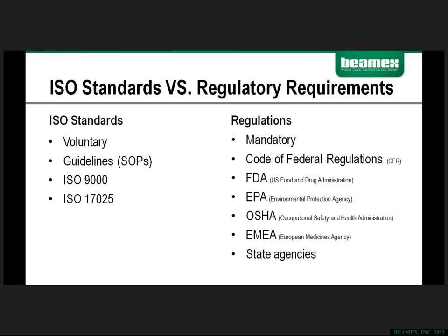I've never had anybody call up and thank me for this, but he had just gotten audited. The auditor was looking over the back of his shoulder, telling him, okay, let me look at this tag. You bring up the tag, let me see the last test results. Easy. You bring that up, shows you the test results. Show me calibrator that was used to calibrate this. So you just click over here, and it shows you. Show me where that calibrator was certified. So you click here, and that shows you what the document number was of the calibration lab that did the certification on your calibrator, which calibrated your tag, so you can follow that chain all the way from your tag all the way back up to the NIST standards. As odd as it sounds, I got a phone call saying thank you after a guy got audited because the auditor was only over his shoulder about 5 minutes and he went off to somebody else.